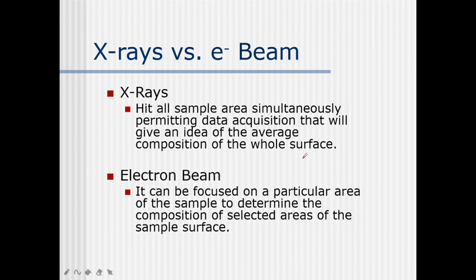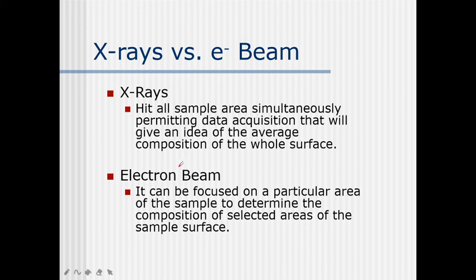Now, X-rays versus electron beam. There are two sources: X-rays and electron beam. X-rays hit all the sample area simultaneously, permitting data acquisition that gives an idea of the average composition of the whole surface. An electron beam, however, can be focused on a particular area of the sample to determine the composition of selected areas. So the electron beam is more specific for selected areas, whereas X-rays provide larger-area data acquisition.